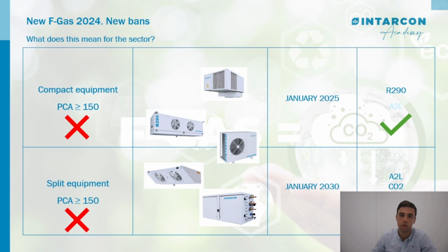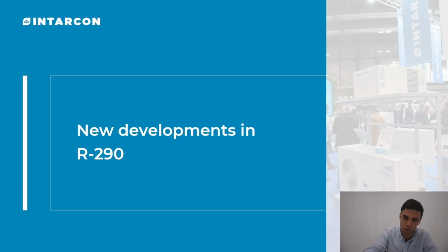The challenge from 2025 in Europe: a ban on the marketing of compact units that use refrigerants with a GWP higher than 150 came into force from January 2025. The same is true for split units from 2030. So what does this mean for the refrigeration sector? Traditional refrigerants with high GWP will no longer be viable, forcing the industry to look for other sustainable solutions.